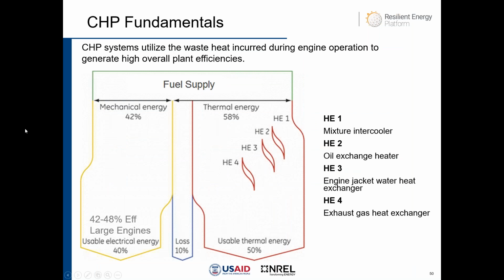The theory behind CHP is to effectively recover the waste heat from the electric generation plant. This is the system. In this system, the electric efficiency is 40%, 5% higher than PREPA efficiency, and that efficiency does not include the transmission and distribution losses that actually are twice the U.S. average. Now, 83% of that 60% that is normally wasted is recovered. And there are many ways to recover it.